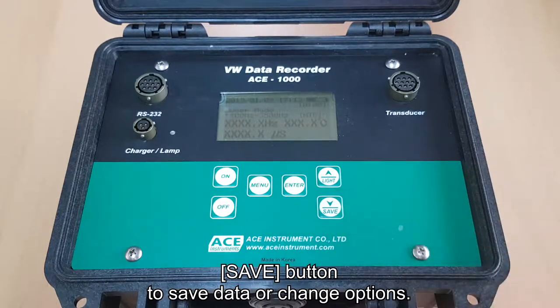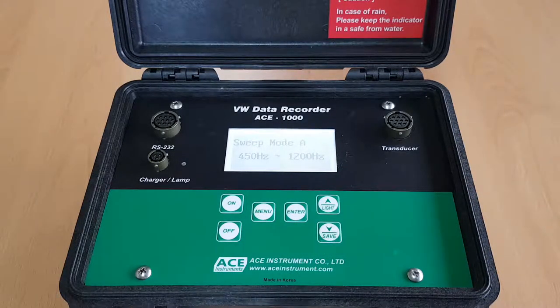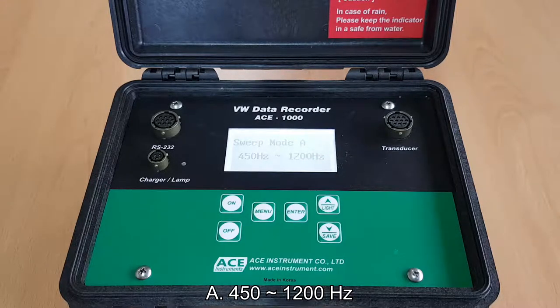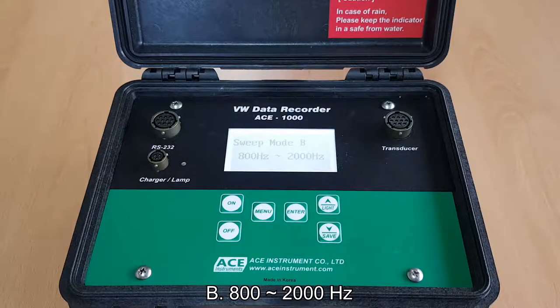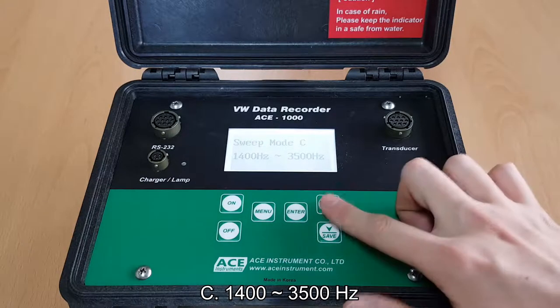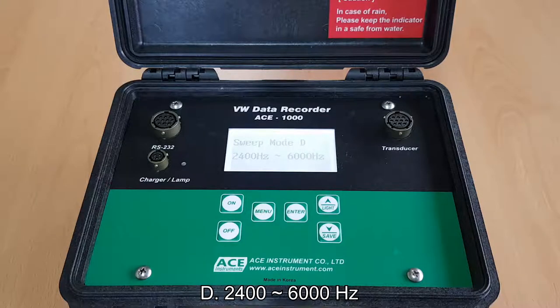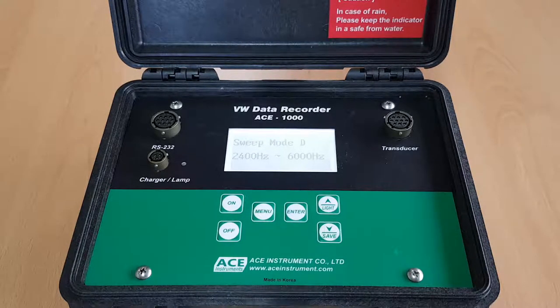The save button is used to save data or change options. In the data recorder menu, the first setting is the sweep mode, which sets the frequency range of the vibrating wire sensor to be measured: 450 to 1200 Hz, 800 to 2000 Hz, 1400 to 3500 Hz, or 2400 to 6000 Hz. The output frequency of the vibrating wire sensor must be within the selected range.